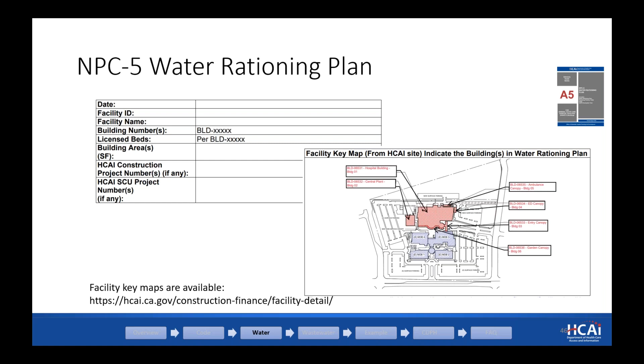So for the documents that we are requiring for review of the water rationing plan, we would like to see an executive summary. We'll show a table of what it looks like, but in the executive summary, we would like to see the existing water and wastewater storage capacity already on site. What would be the additional proposed water and wastewater storage based on your water rationing plan, which ties into the third point here, the anticipated emergency usage, which comes from your water rationing or conservation plan. Then the important thing that CDPH is looking for is what services are affected under your rationing plan during this emergency, and also information about water replenishment and tanker truck arrangements that have been made to continue the 72 hours of operation.